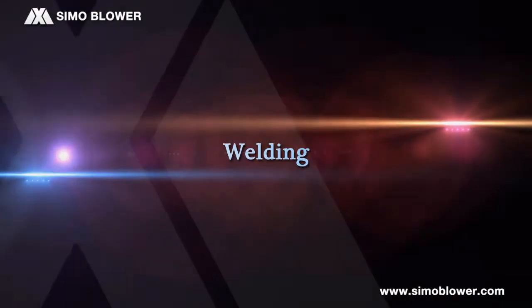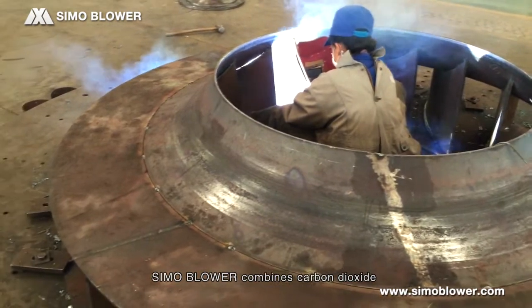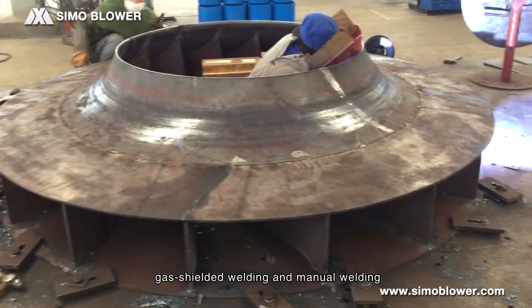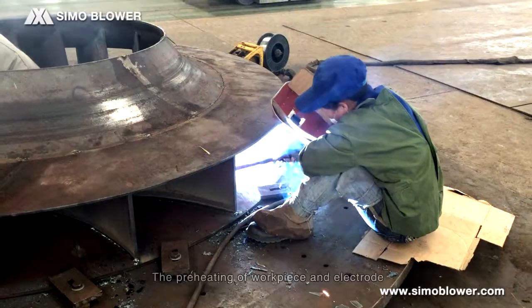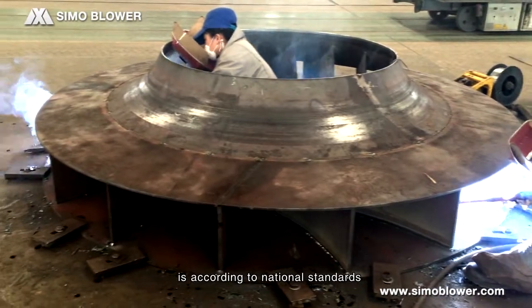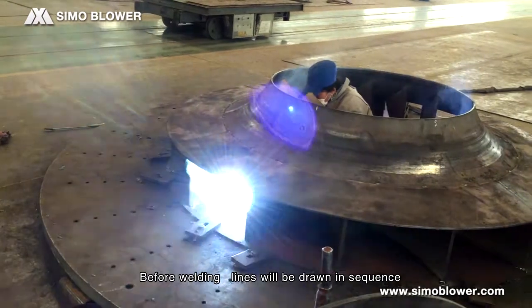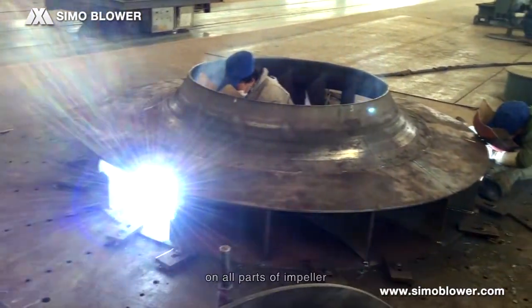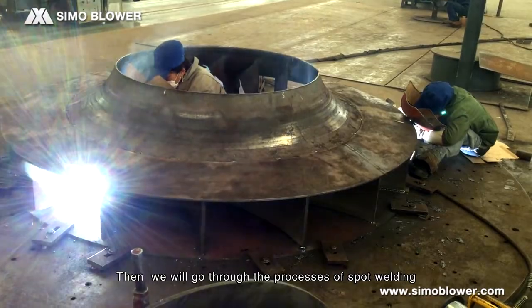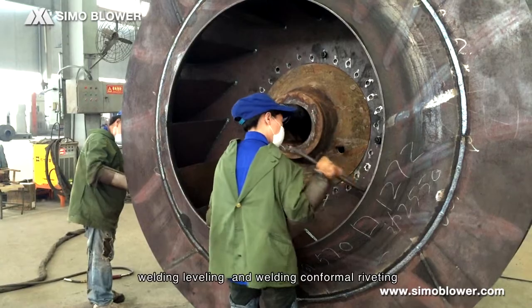Welding. Simo blower combines carbon dioxide gas-shielded welding and manual welding. The preheating of workpiece and electrode is according to national standards. Before welding, lines are drawn in sequence on all parts of the impellers. Then we go through the processes of spot welding, welding leveling, and welding conformal riveting.